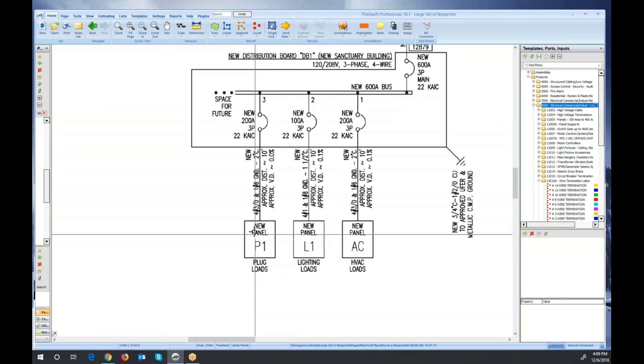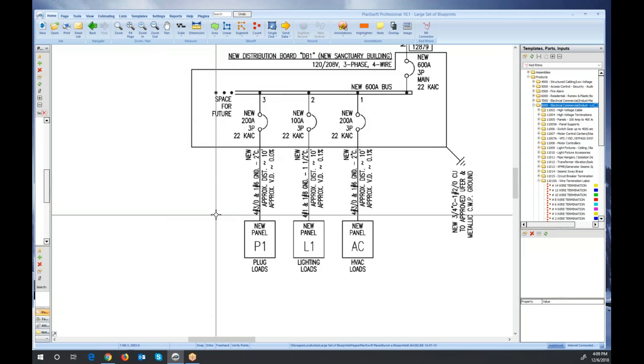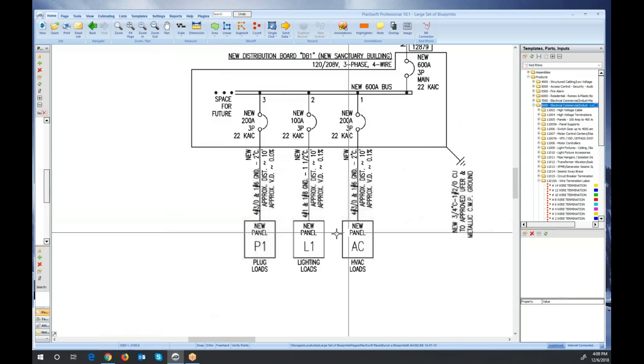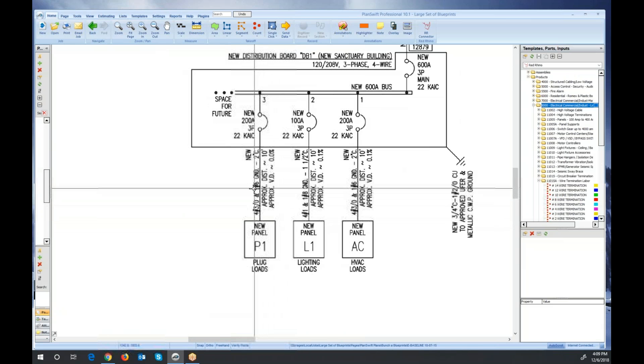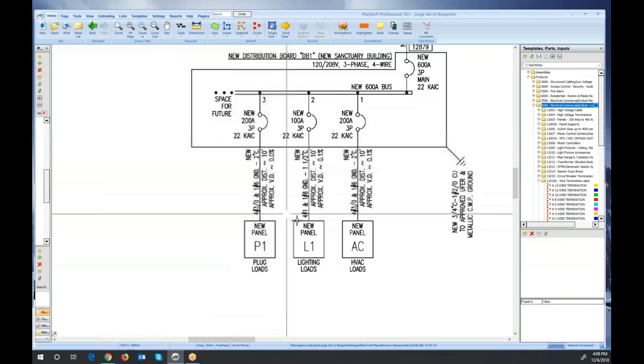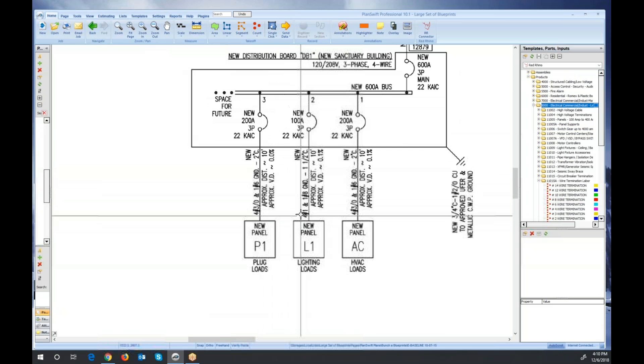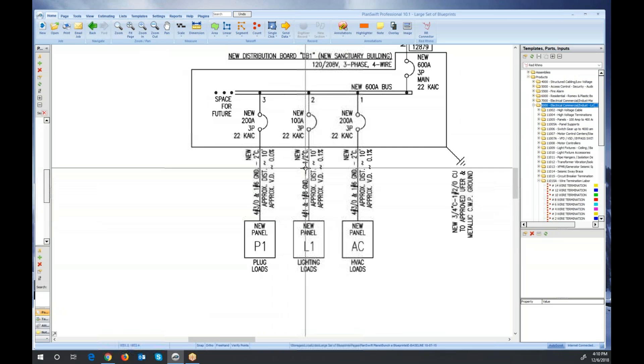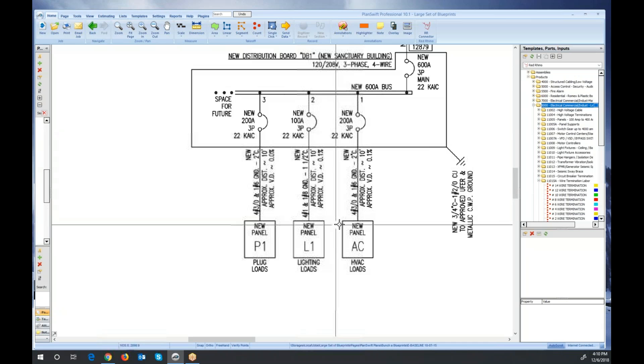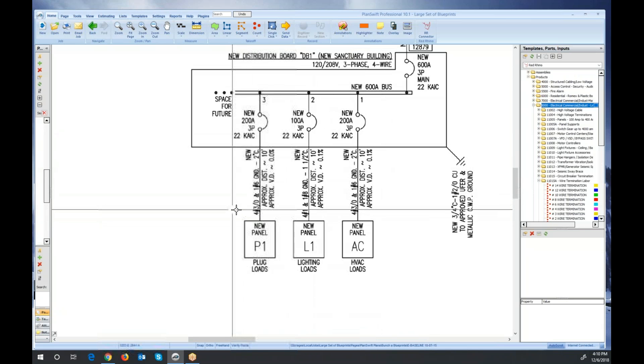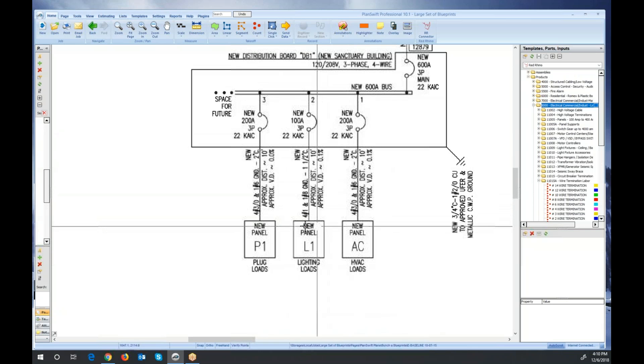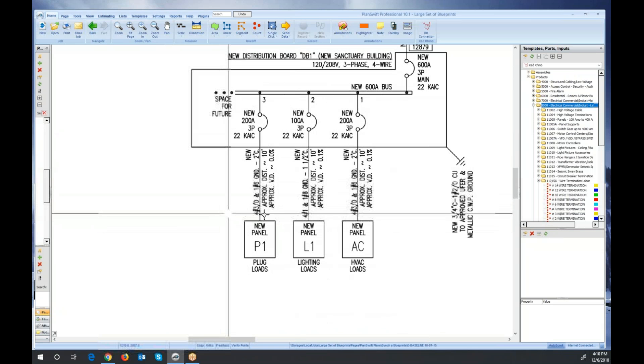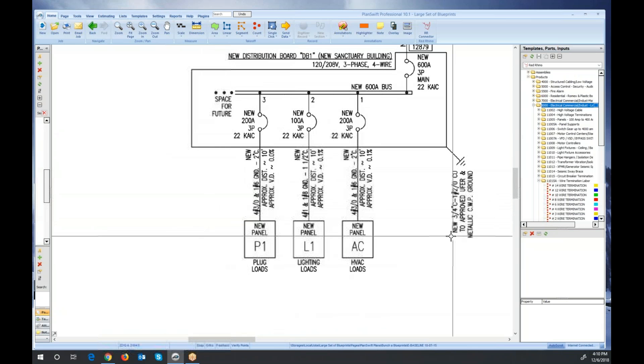It doesn't tell you that you need to terminate wires in the panel, but you do. This one says four 3-aught and one number six ground, it's a two-inch. This one says four number one and one number eight and an inch and a half, and four 3-aught again. So I'm going to count all the 3-aughts at one time across here, and then I'll move on and count the rest of them.